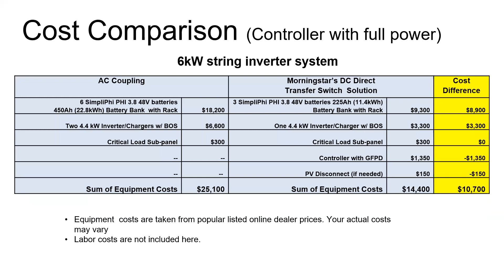So this example makes even more sense. Again, the 6 kilowatt array, 2 inverters with AC coupling. That's just per the battery-based inverter's requirements of how much you need to AC couple that array into the multi-mode inverter. And per those 2 inverters, we need 6 batteries to cover the output of the inverter into the critical loads panel.